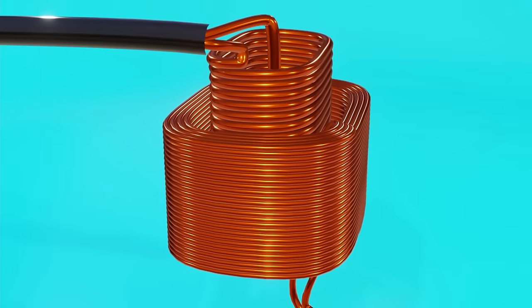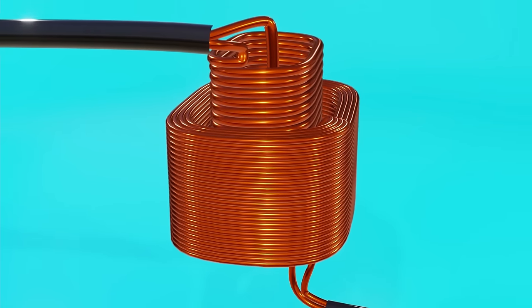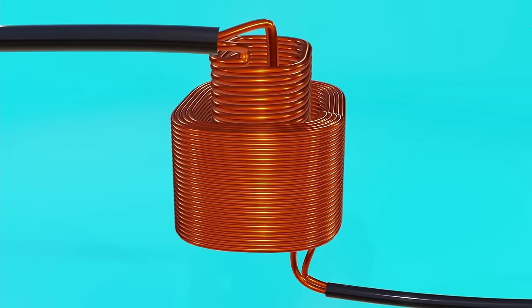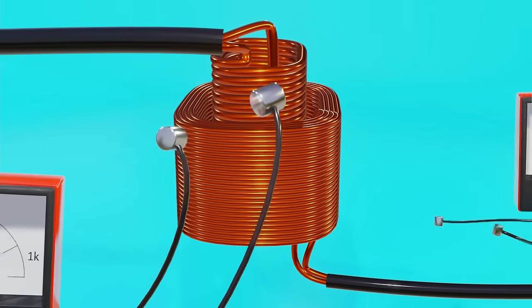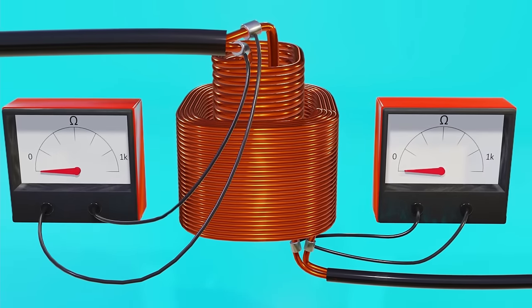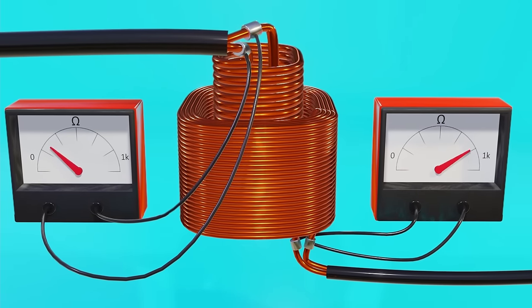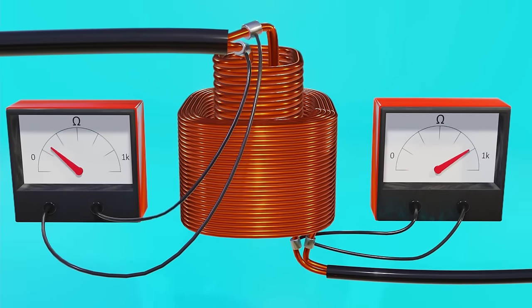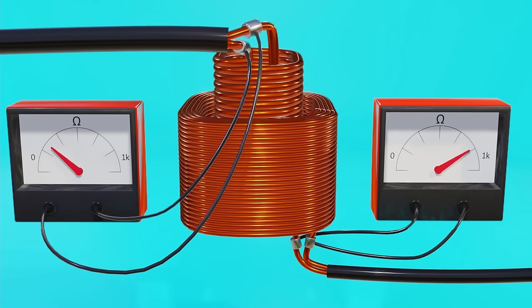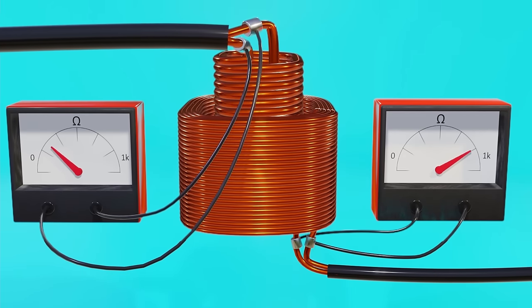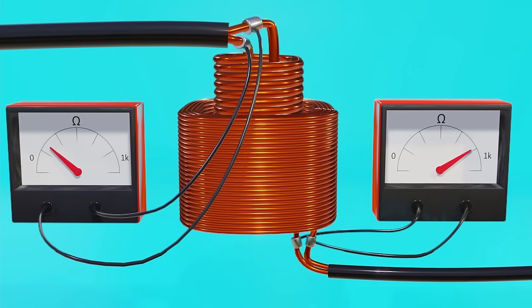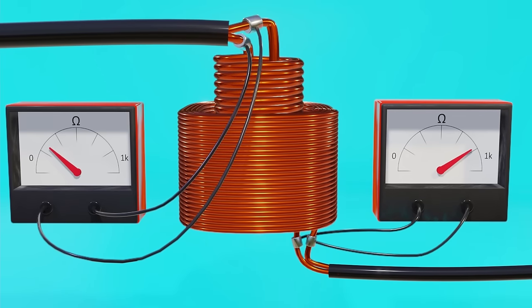This same difference in diameters means that in case we have a transformer in which we do not know which terminal corresponds to which coil, since they are generally covered, we could measure both resistances and deduce that the one that is smaller corresponds to the coil with the fewest turns, since a greater cross-sectional area and a smaller length means less resistance.